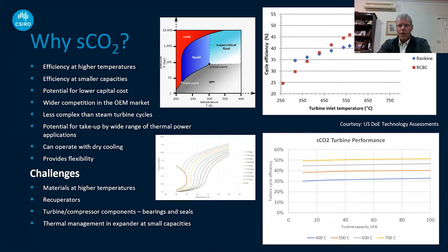First of all, what is supercritical CO2? At around 31 degrees Celsius and 7.38 megapascals, CO2 turns into a supercritical fluid, and that has a number of advantages. If you think of a typical Rankine cycle steam turbine, around 42% efficiency, the rest of that energy loss, maybe 50%, goes out as hot fluid, hot water. But you've got the advantage in that cycle of only very low pumping power because you're pumping an incompressible liquid.